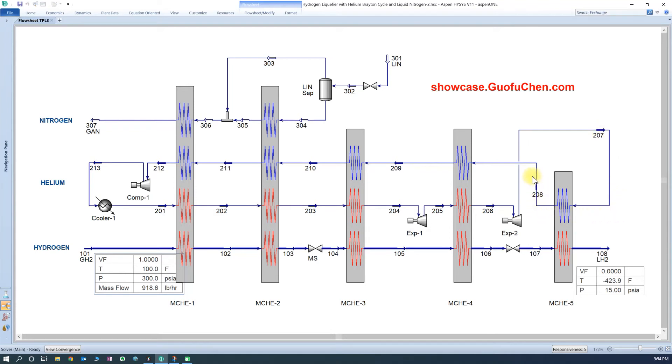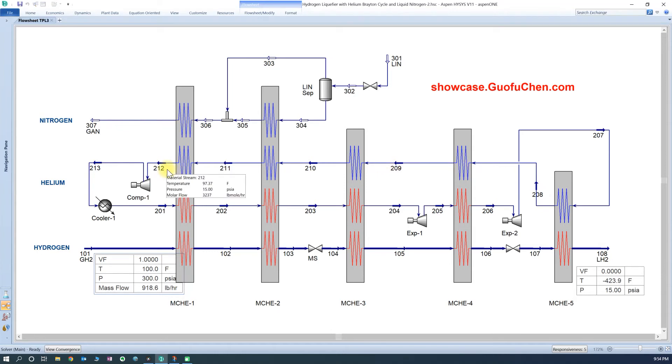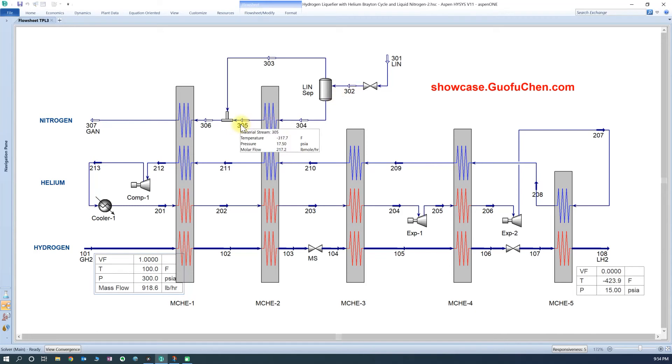After helium is warmed up in the main cryogenic exchanger, it is sent to the compressor and the cooler to form a closed loop. Liquid nitrogen is used to pre-cool both helium and hydrogen. It is then vented to atmosphere after it is warmed up to ambient temperature.